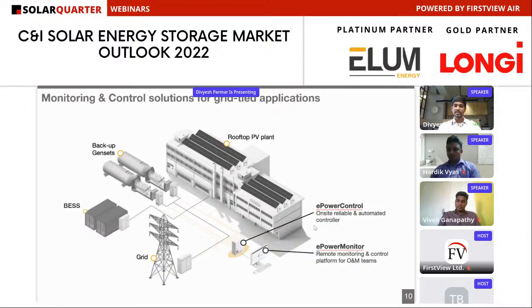Here you can see EPower Control, which is our microgrid controller, communicating with the PV inverters, genset controllers, PCS inverters, and grid AC meters over Modbus RTU or TCP. While doing so, it takes care of maximum PV penetration, minimum genset loading, as well as SOC-based charging and discharging of the batteries.